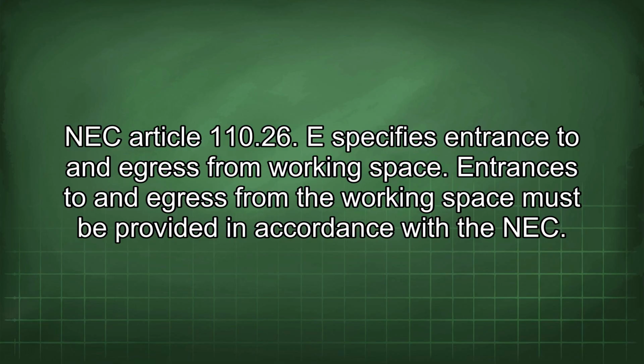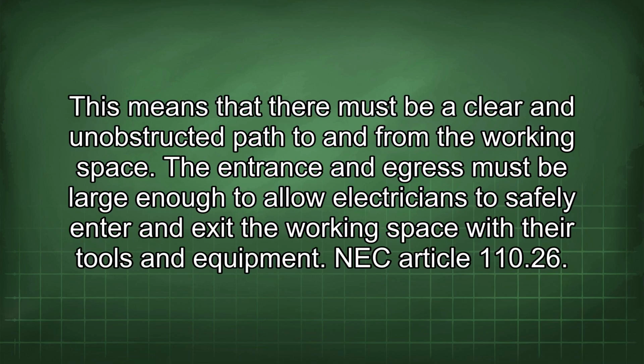NEC Article 110.26 E specifies entrance to and egress from working space. Entrances to and egress from the working space must be provided in accordance with the NEC. This means that there must be a clear and unobstructed path to and from the working space. The entrance and egress must be large enough to allow electricians to safely enter and exit the working space with their tools and equipment.